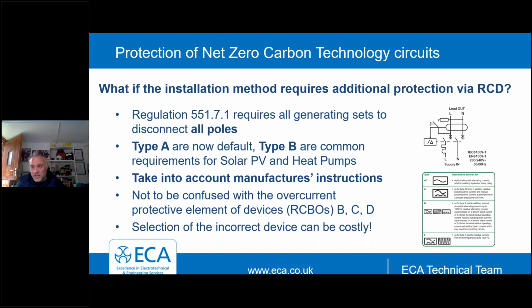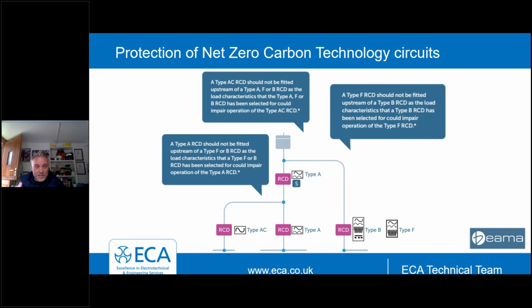Don't be confused with the selection of RCDs and RCBOs, the protective curve, B, C, and D, with the type A, type B, type F, etc. So just ensuring that we select these products right, otherwise it can be costly. Important that when we select and erect RCDs, they are the correct one and we put them in the right way. And we've got this image of our friends at BEAMA who have a great guide on selection and erection of RCDs in general. And here it's clearly stating that if you're going to use a type B or a type F, you really shouldn't be using an RCD in front of that because of blinding. So careful selection now. This may make a difference when you are selecting boards, different consumer units doing different jobs. You might have to split the tails, for example, but this is a great guide as well from our friends at BEAMA. So where RCDs are required, it's really important that we select them in the right way and we wire in the right manner as well.